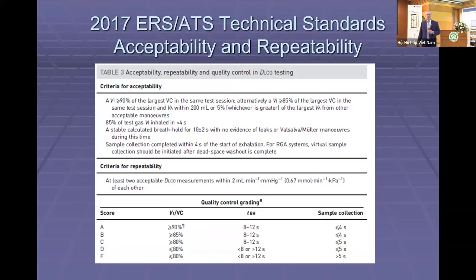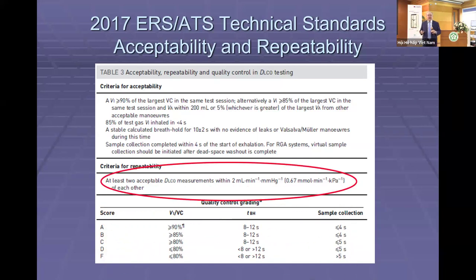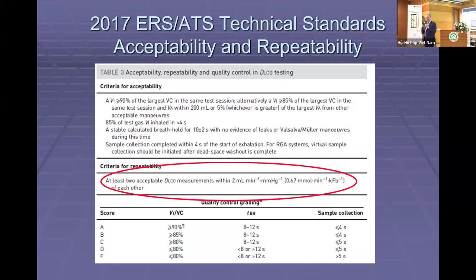There is an acceptability criteria, which includes taking that deep breath to 90% of the largest vital capacity. There's also a repeatability criteria: at least 2 maneuvers must be repeatable within 2 units of one another using millimeters of mercury. In parts of the world using SI units — kilopascals — that repeatability is less than 1 unit (0.67 kPa).